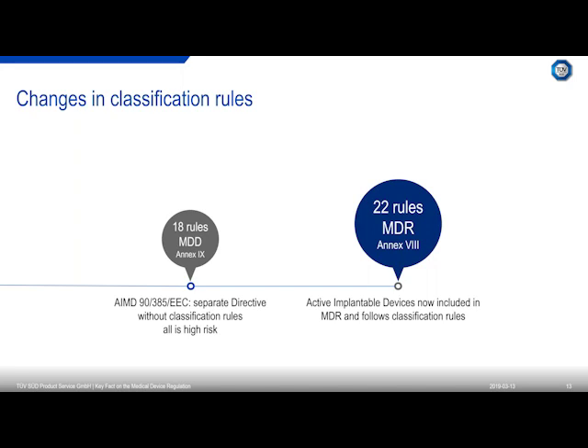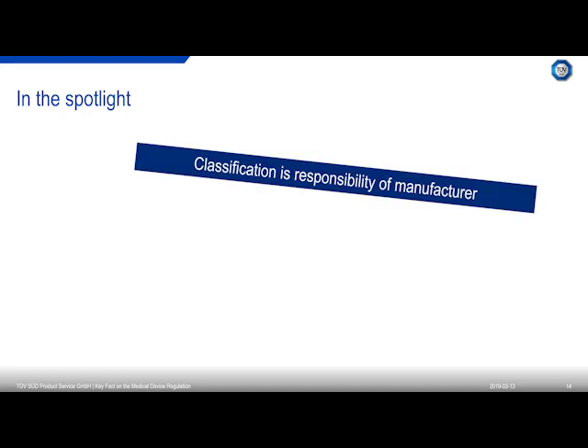First of all, it's very important that you go through Annex VIII from the beginning on, because there are some definitions that you need to take into consideration. I will highlight some things that are important from Annex VIII. The classification is the responsibility of the manufacturer. It is not the responsibility of the notified body. A notified body is there to challenge the classification the manufacturer did. And if there is a dispute, then notified body, authority, and manufacturer need to come to an agreement through a certain process, but we'll come to that later.